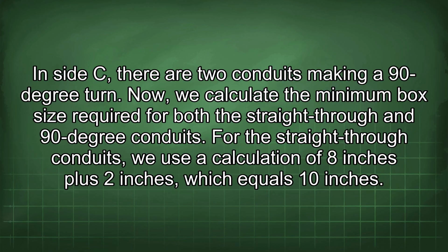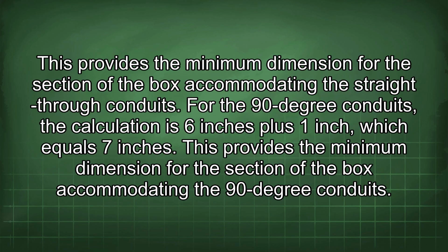Now, we calculate the minimum box size required for both the straight-through and 90-degree conduits. For the straight-through conduits, we use a calculation of 8 inches plus 2 inches, which equals 10 inches. This provides the minimum dimension for the section of the box accommodating the straight-through conduits. For the 90-degree conduits, the calculation is 6 inches plus 1 inch, which equals 7 inches. This provides the minimum dimension for the section of the box accommodating the 90-degree conduits.